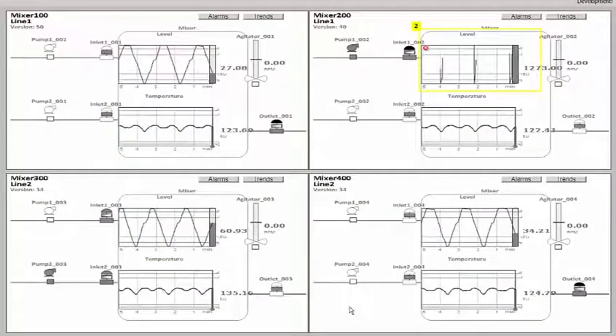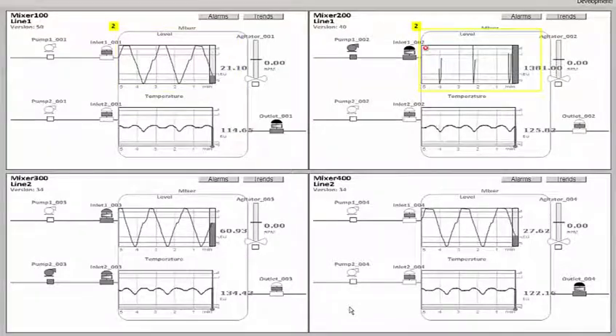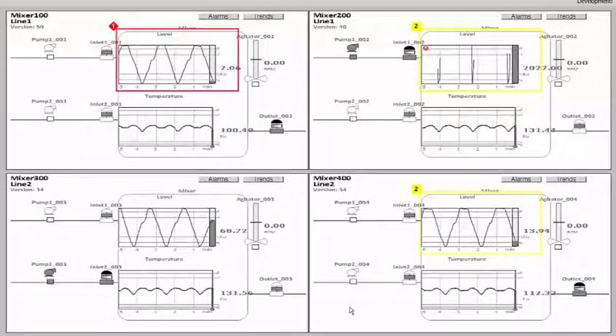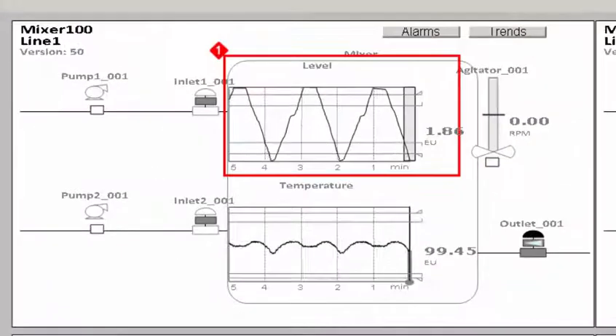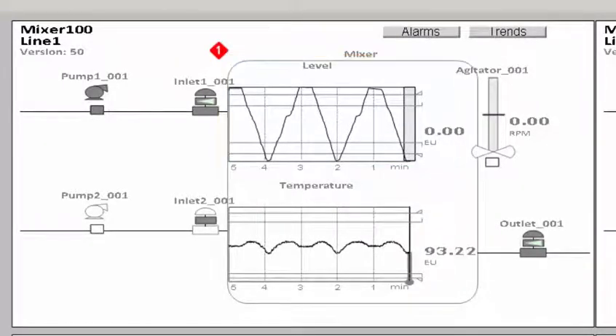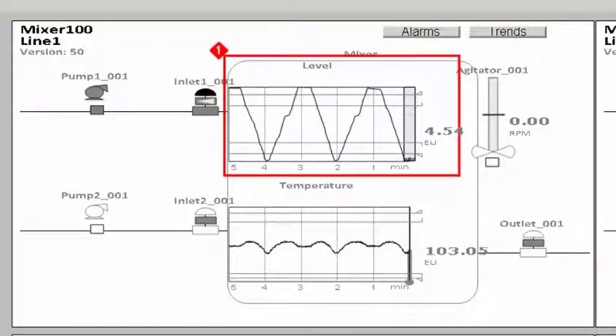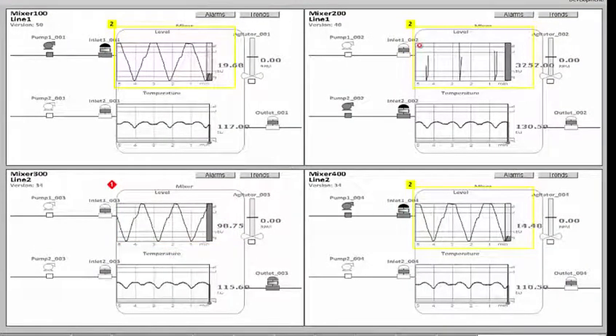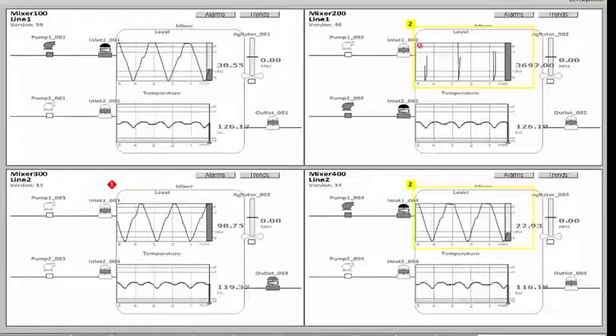Here's an example of our alarm border animation in action. You can see Mixer 100 and Mixer 200 have a level 2 alarm. Mixer 400 just came up with a level 2 alarm. Mixer 100 just came up with a level 1 alarm — you can see it's flashing because it's an unacknowledged alarm. If I acknowledge that alarm, it would stop flashing, indicating that the operator has acknowledged it. The whole idea of the alarm border animation is to bring the operator's attention to a piece of equipment that is in an alarm state beyond just showing information in the actual alarm display.